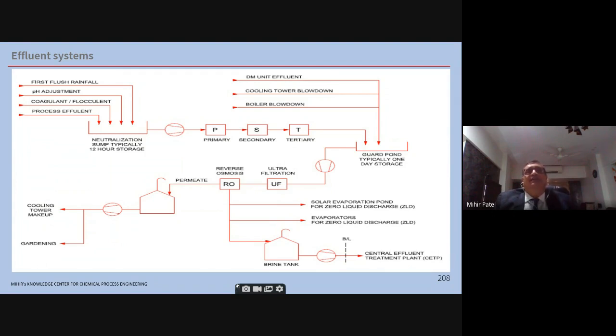Again, the secondary treatment is an OEM item. It is not easy to design these biological treatments. Conventional biological reactors, the MBBR, which is there right now, these are very patented types of designs, and one should always go with the OEM there. Tertiary treatment is nothing but a polishing step. So you have an activated carbon filter here, which basically polishes. This entire thing is a complete package item. Please remember that. At the outlet of the tertiary, you have a guard pond, which is nothing but a final guard pond. As indicated, it's a guard pond. So if there are any slippages, you can use this guard pond so that you don't send out any contaminated effluent from your plant.